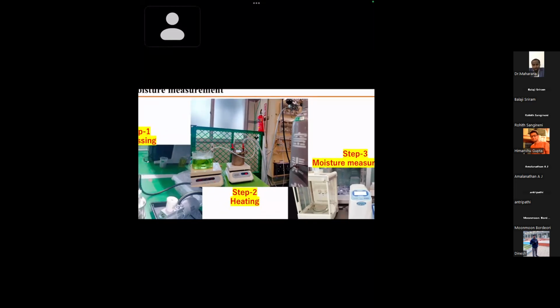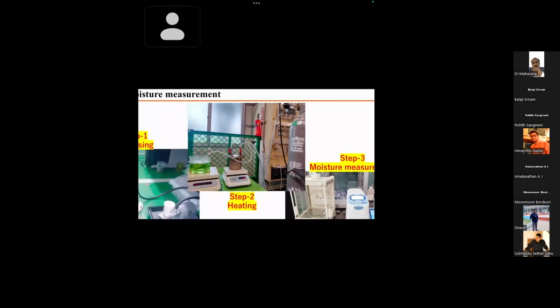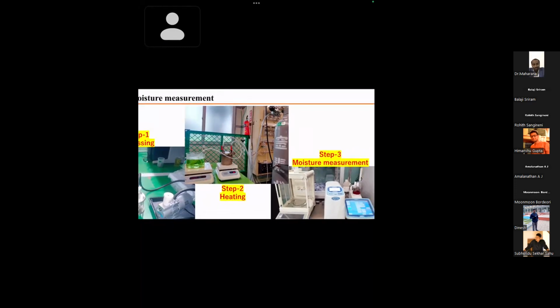FR3 oil. It depends on the actual scenario, like how long we can wait, or maybe until it evaporates. If you increase the time for which you pass the water vapor, does it affect the amount of moisture it is absorbing? Yes, that is a good question. It actually depends on the time. If you put it for half an hour, you can expect up to, let's say, 100 ppm. If you keep it for 2 hours, maybe you can get an actual moisture of 300 ppm.